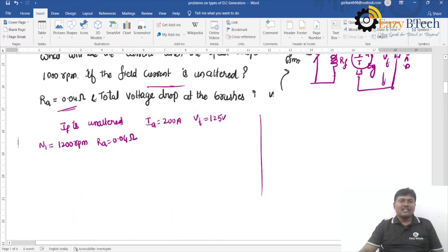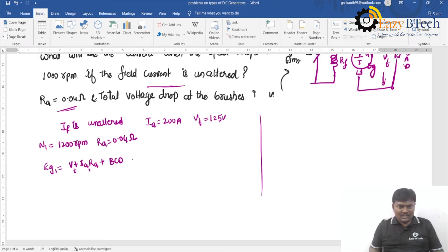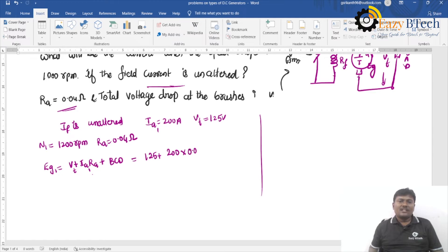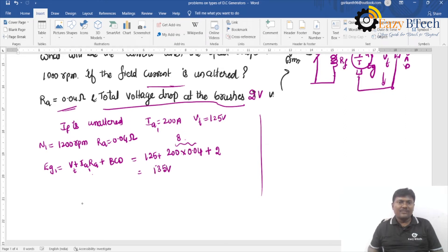Calculate EG1 using: EG1 = VT + IA1·RA + brush contact drop. VT = 125V, IA1 = 200A, RA = 0.04 ohms, brush contact drop = 2V. So 200 × 0.04 = 8, then 125 + 8 + 2 = 135V. Therefore EG1 = 135V.